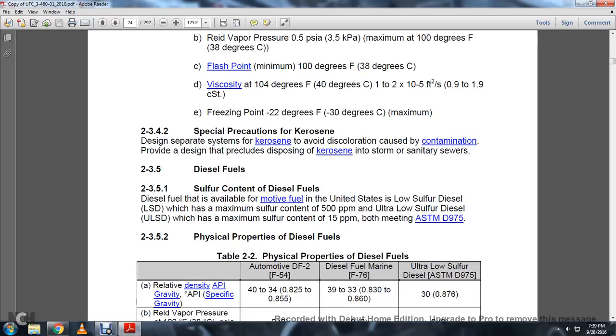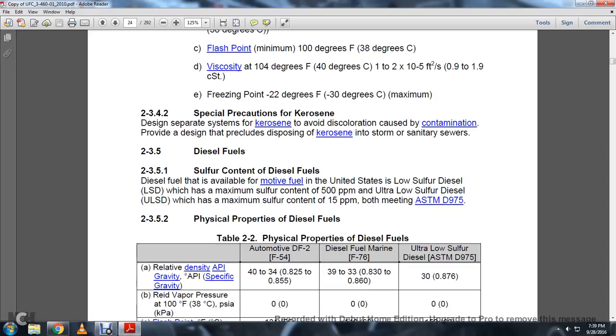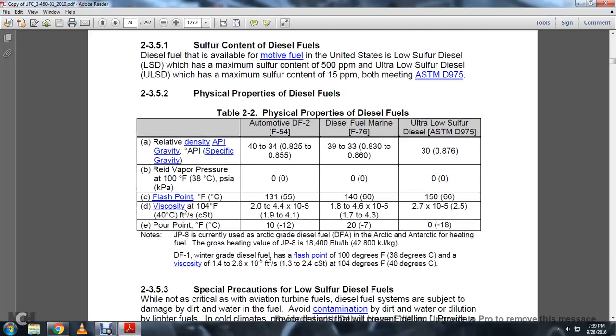2.3.5 Diesel sulfur content. Diesel fuel is available as motor fuel in the United States as low sulfur diesel, or LSD, which has a maximum sulfur content of 500 ppm, and ultra low sulfur diesel, ULSD, with a maximum sulfur content of 15 ppm, both meeting ASTM D975.